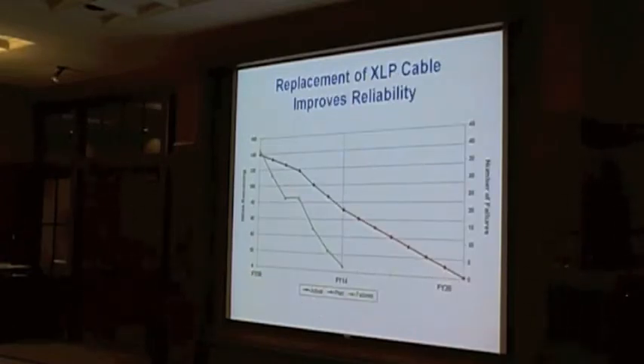I talked a little about the XLP cable, the cross-linked polyethylene. One thing to know is it's been in place since the 60s, and we quit using it in the early 80s. The cable, because of the insulating material it's made of, has become brittle in some respects, which affects its insulating capability and results in cable failures and faults.